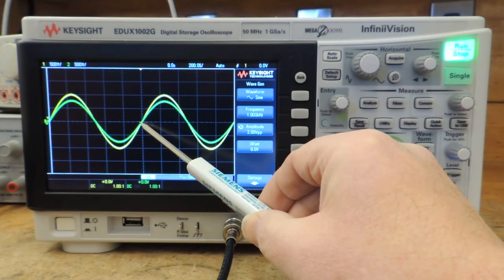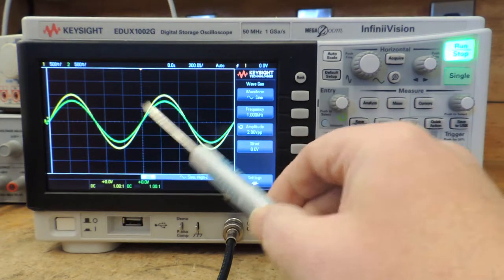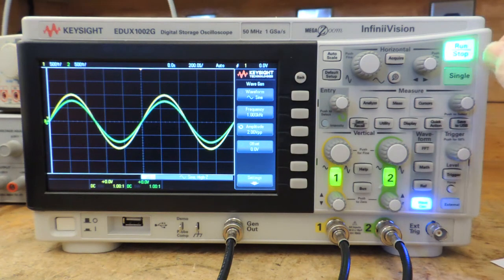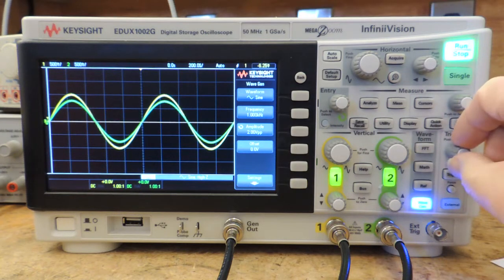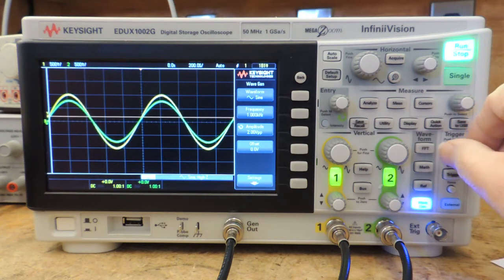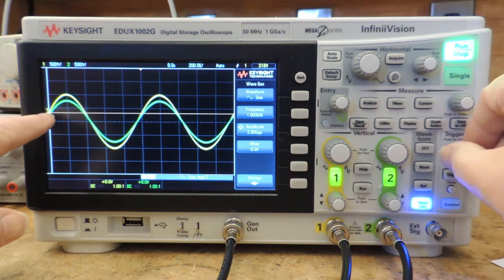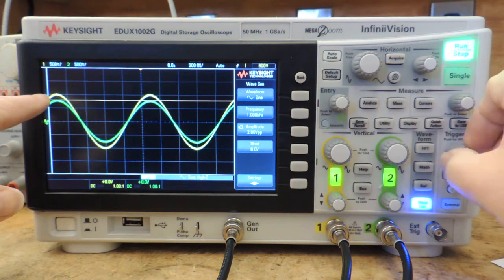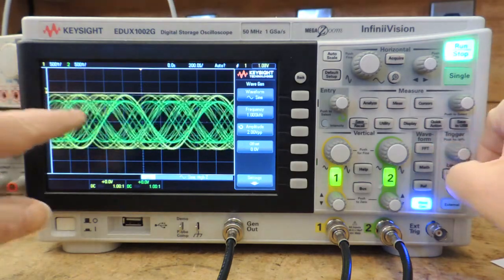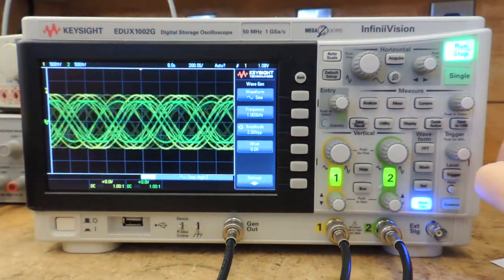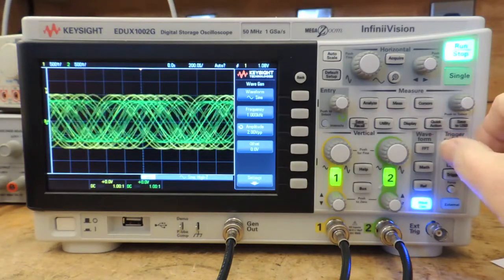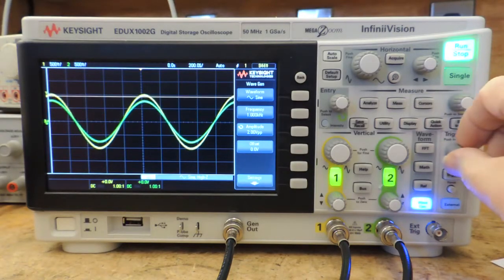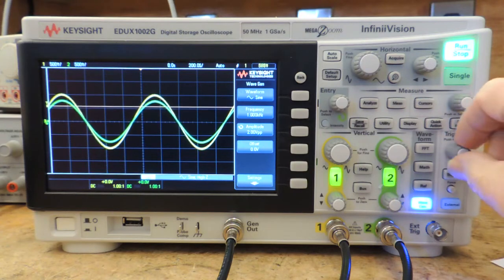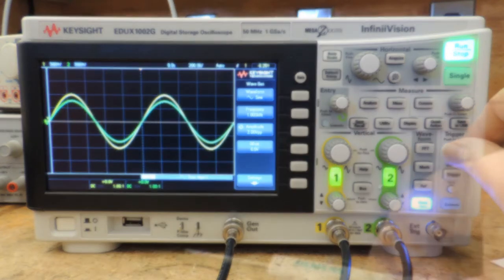One of the things they say in the instructions is the waveform could be rotating or jigging back and forth, and that can be caused by the trigger level. So here we have the trigger settings. If I rotate the trigger knob, you can see that the line for the triggering point is moving upwards. If it moves above the waveform, it doesn't know where to start drawing the waveform. So that trigger line needs to be in your waveform, and preferably we'd like it somewhere on the zero line.